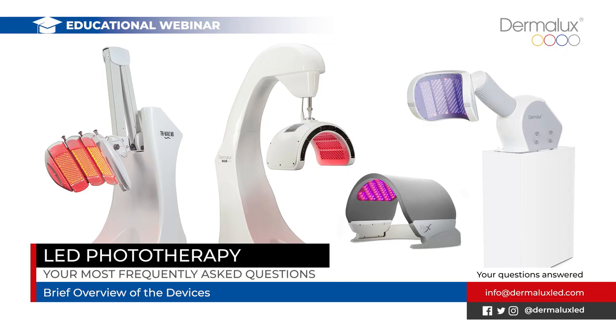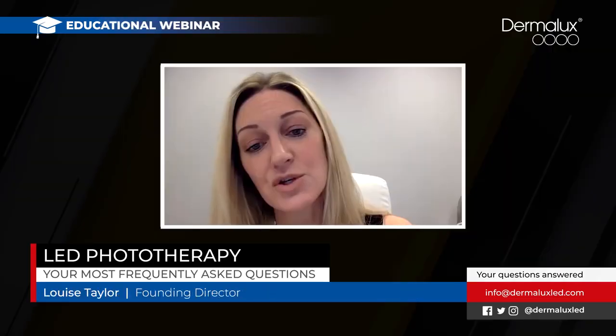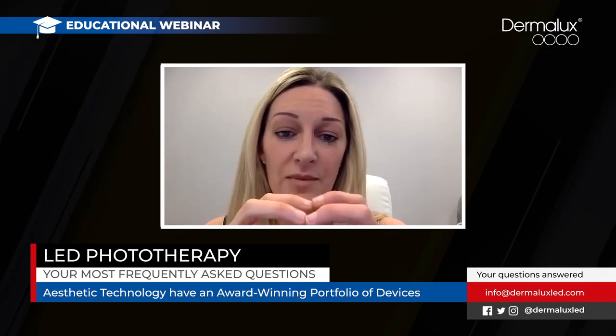But these are delivered via our unique single wavelength LEDs, our proprietary technology, which, as we said, is really important when you're looking for a device. The difference between the four systems that we have is the power. More power means more requirement for cooling technology to maintain stable energy delivery over time, but also to protect those LEDs from early degeneration. We've invested heavily in that technology to make sure they deliver a safe, stable treatment and have a long lifespan as well.